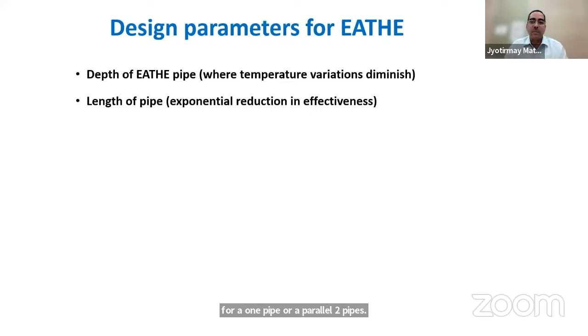Sometimes, like in Jaipur, we have determined that an optimal length is 60 meters. So if you need more than 60 meters, if you have to blow more air, you lay parallel pipes. But when I say parallel pipes, the diameter of the pipe becomes very important, because it plays an important role in determining the energy consumption of my blower. If I'm taking too small a pipe, my friction losses would be very high, and therefore the blower's energy consumption would be high.